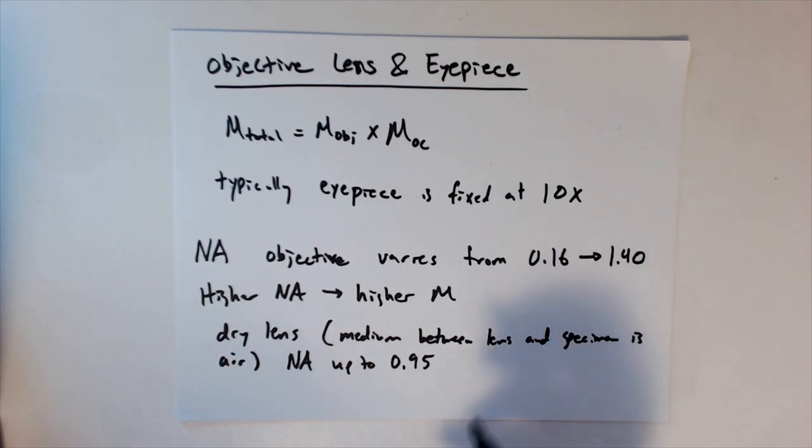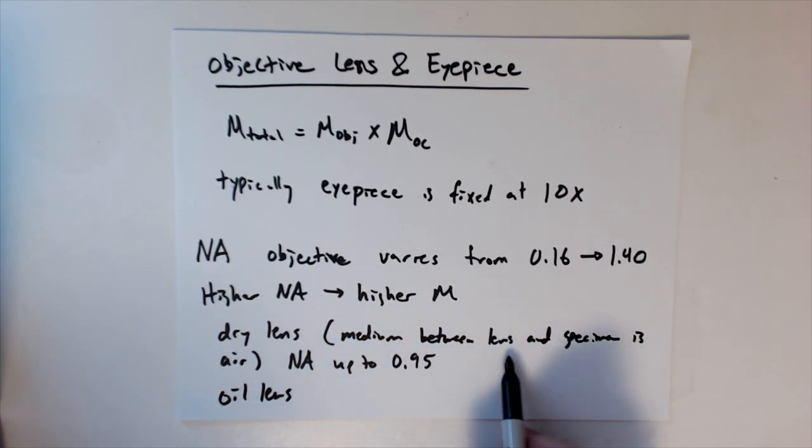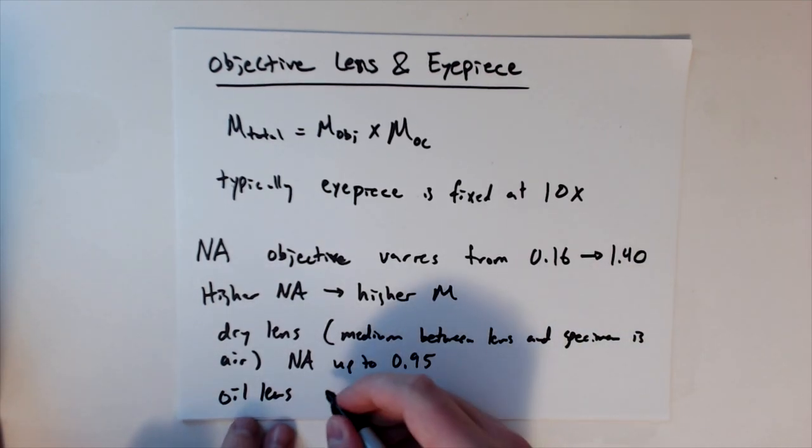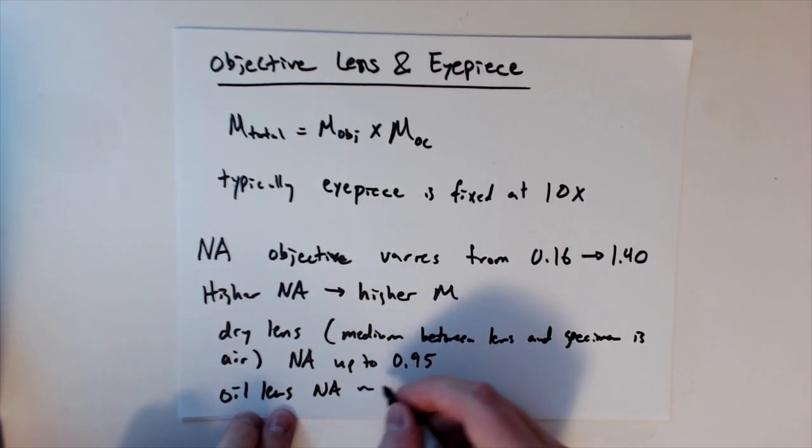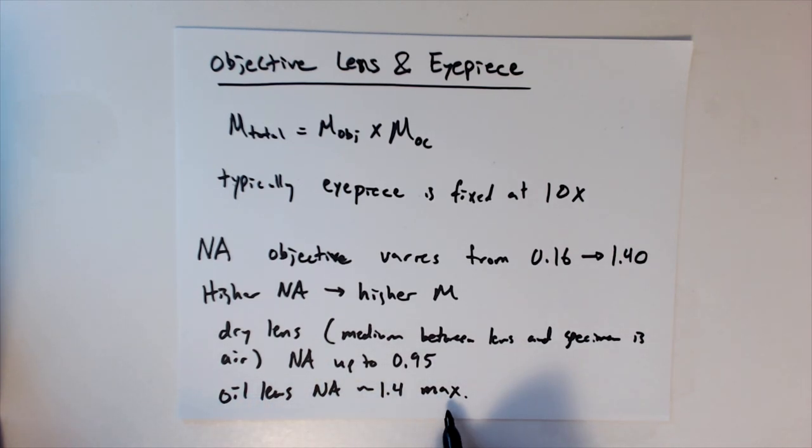So that means that if we use oil lens, so that's where we have oil between the lens and the specimen, then we can get an NA of up to 1.4 max. So that's the upper maximum. I mentioned this before, but objectives are a barrel, and they have a series of lenses within them. In the best cases, we have oil, and then air only gets us up so far in terms of the numerical aperture.